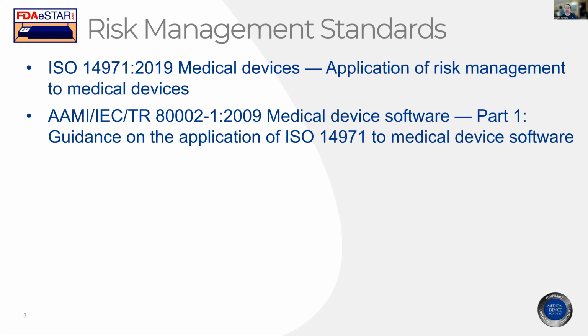And if you want to know, will this work for all classifications of devices? Absolutely it will, because one of the best jobs I've ever seen a company do right out of the box for a brand new product was in an internal audit of an AED. So this is a class 3 PMA product. Right out of the box, they took all the risks that were in 80002-1 and applied them, and that was their first pass. And the FDA gave them their PMA.